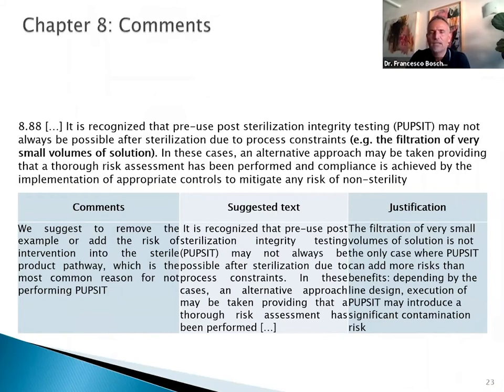In this version of the annex, EMA is open to some more flexibility about the consideration of the real need and the risk associated with PUPSIT. The annex says that it may not always be possible after sterilization to run PUPSIT due to process constraints, for example, the filtration of small volumes of solution.